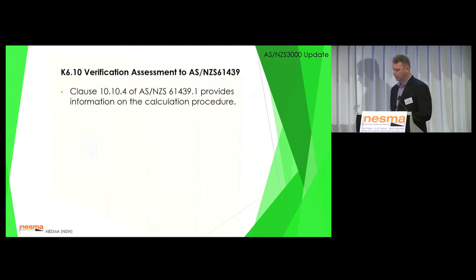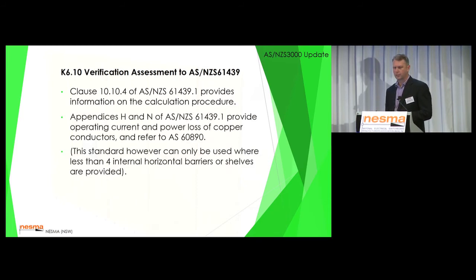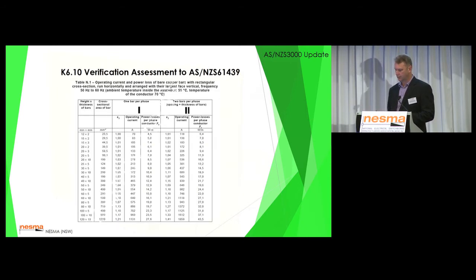Verification assessment. So clause 10.10.4 provides information on this calculation procedure. A lot of the details are still referred back to 61439 or 3439 for tables or appendices. So appendices H and N provide operating current and power loss of the copper conductors and also refer to 60890, which is a temperature rise calculation. So here's an example of table N. So this is put back into 61439.